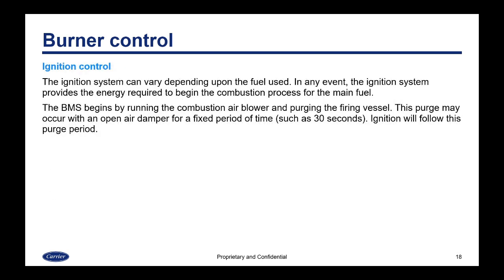The ignition system can vary depending upon the fuel used. In any event, the ignition system provides the energy required to begin the combustion process for the main fuel. The BMS begins by running the combustion air blower and purging the firing vessel. The purge may occur either with an open or closed damper for a fixed period of time, depending on how much air you're trying to move through the vessel, and ignition will follow the purge period.